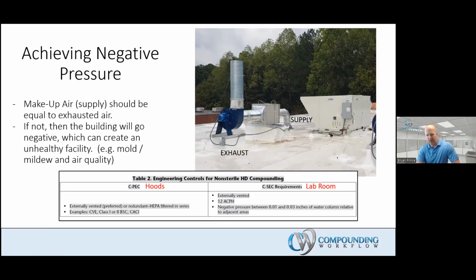And if you haven't integrated USP 800 compliance yet, there is nothing about your existing air handling system that was ever meant to do that much external exhaust air with fresh. So they call me Bad News Brian at PCAB during the workshops because I get to tell you the bad news. If you throw the air out, you got to put the air back in, and that system right there starts at a minimum of $30,000. It goes up to $40,000 and $50,000 depending on how much air you're actually having to put in the space.